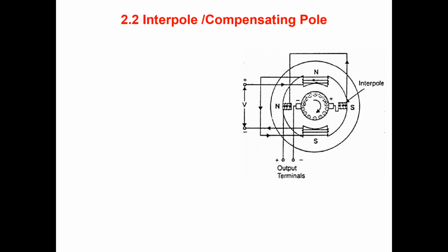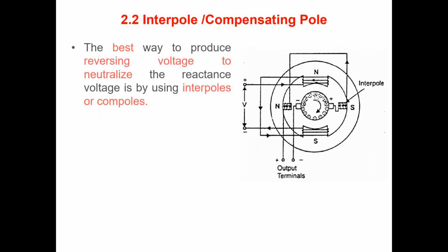If we say that from positive we take away current, but north is connected to positive and south is connected to negative through this positive and negative brush of our commutator, so that it can neutralize the armature current. If armature current is neutralized, armature reaction is neutralized, it will improve the commutation. That will be the basic funda behind this.